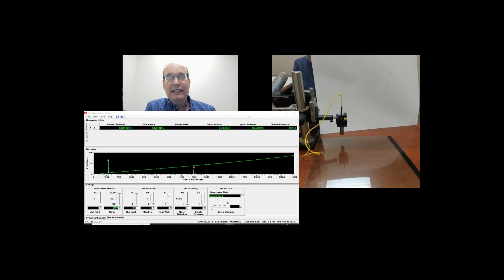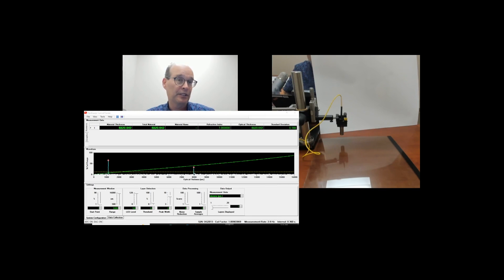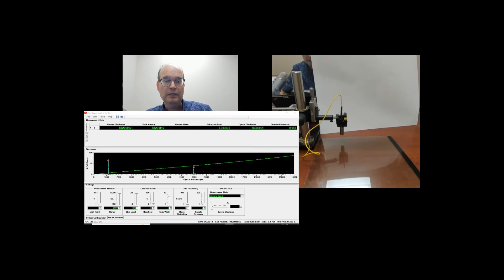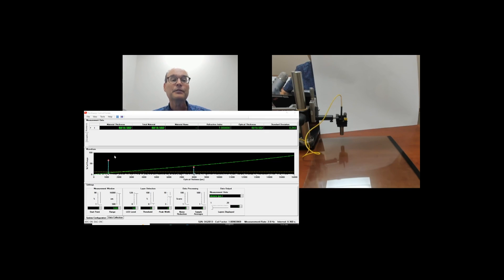It provides a peak in front of all the surfaces that the probe sees. And it doesn't matter where the probe is — it's always in the same place. So if the probe moves up, the distance between that first peak and the first signal will show up as a change in depth. For example, what we have on screen here — this first peak — is the reference signal generator peak.